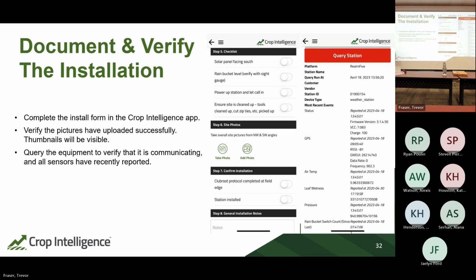So yeah, in the query, what you're looking for with the probe, that screen doesn't show it, but you'll see each of the sensors. They'll probably all be a 0.9 something, with the wet slurry. As long as they're all showing that, you probably don't have any air pockets. It should be okay.